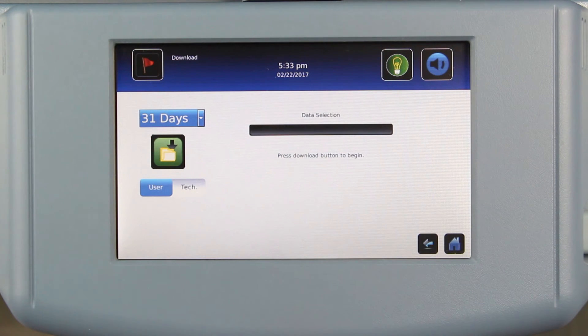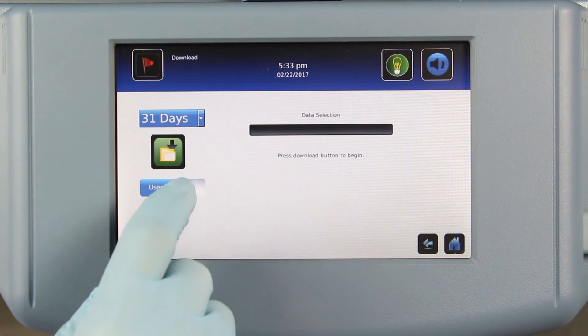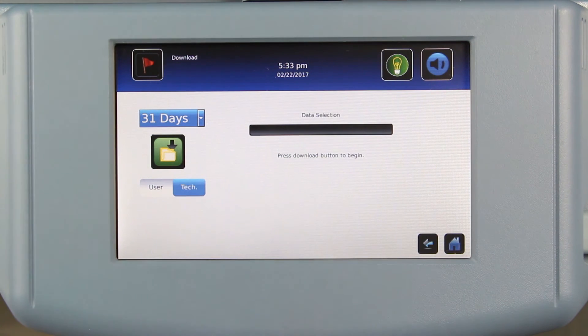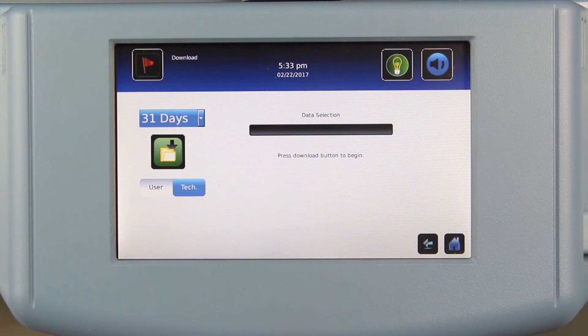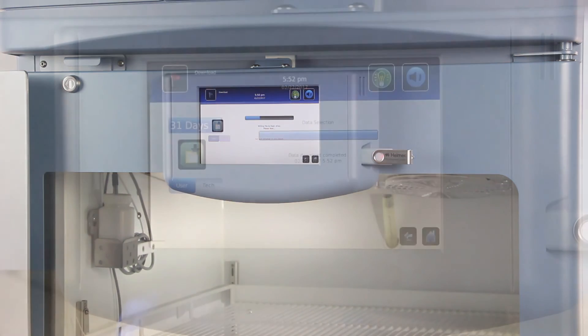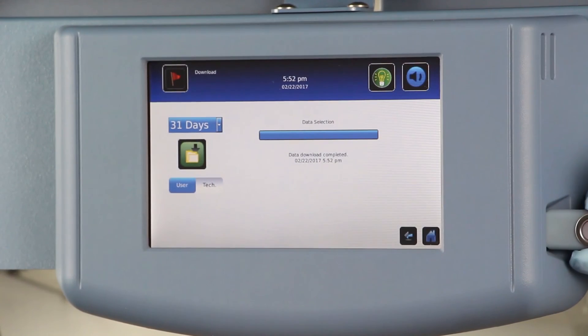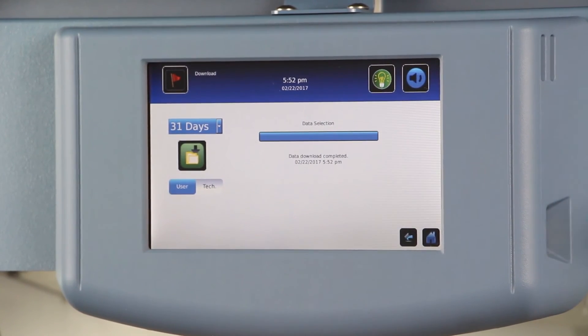In addition, there is now a choice of user or tech downloads. Downloaded user files include temperature data and event log information, plus additional files depending on the configuration of the unit. The tech files provide historical data that can be helpful for diagnostic purposes.